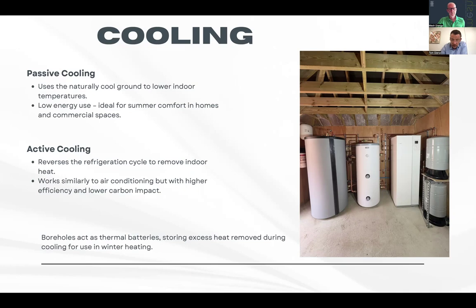With a heating and cooling system, the design of the borehole is very important, because if the cooling demand is higher, you might need to oversize the array to be able to cope with this extra energy you are trying to discharge into the geology. And then, importantly, the type of geology is very important to be able to take that.